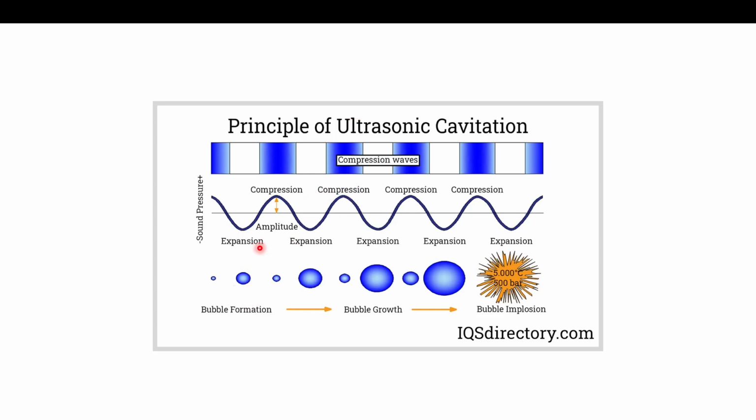Bubble formation takes place. The sonic waves have a particular amplitude, which is variable; the user can set the amplitude. Due to expansion and compression as the wave travels, unequal-sized cavitation bubbles are formed, and then suddenly the bubble explodes, thereby disrupting the cell walls nearby.